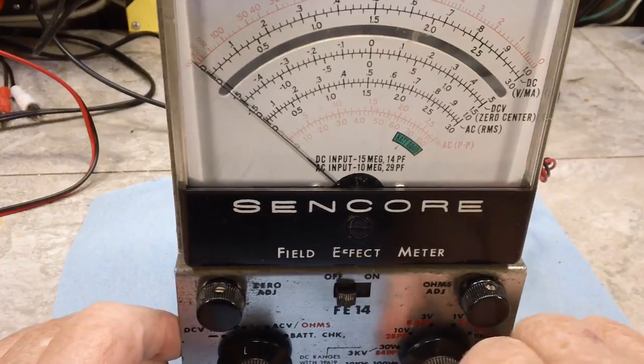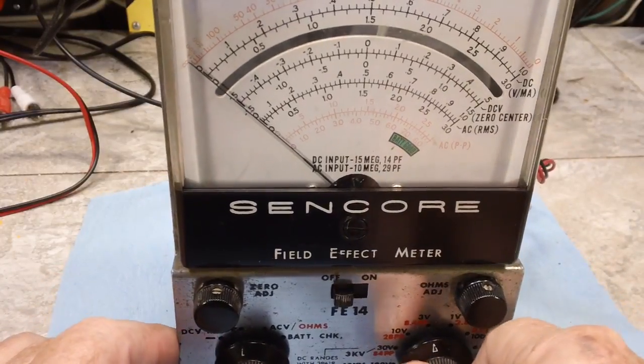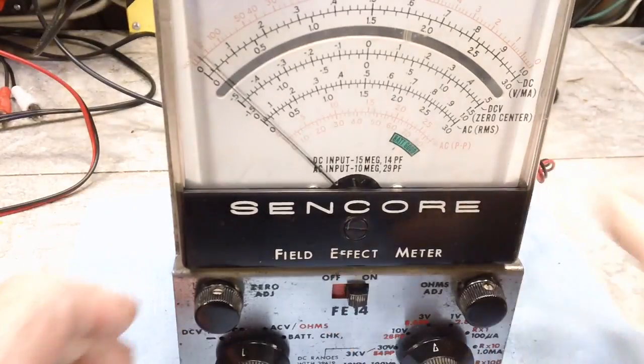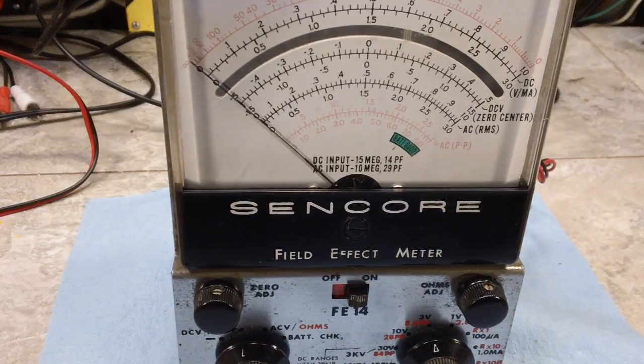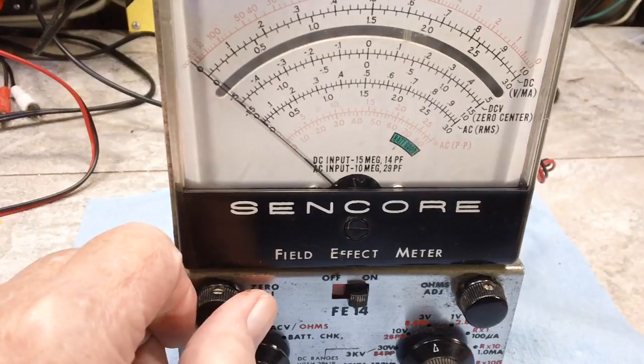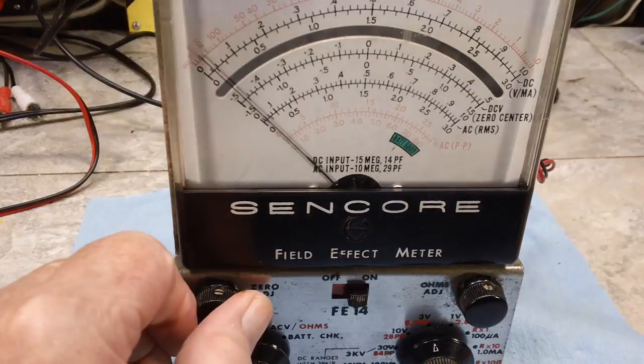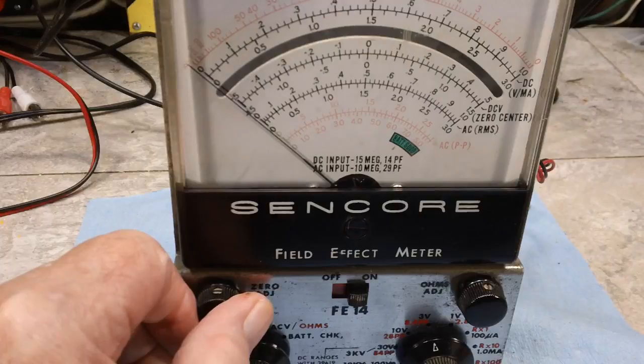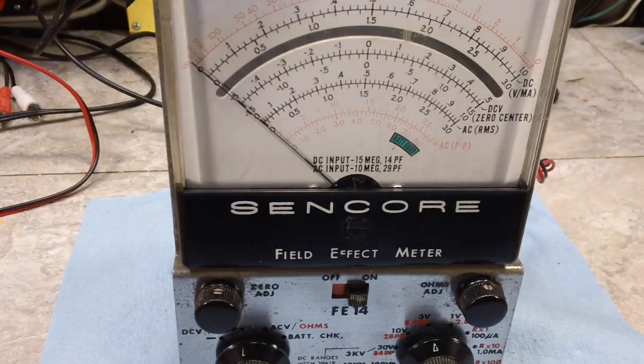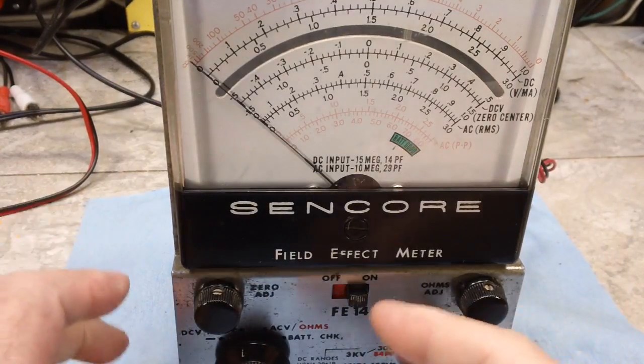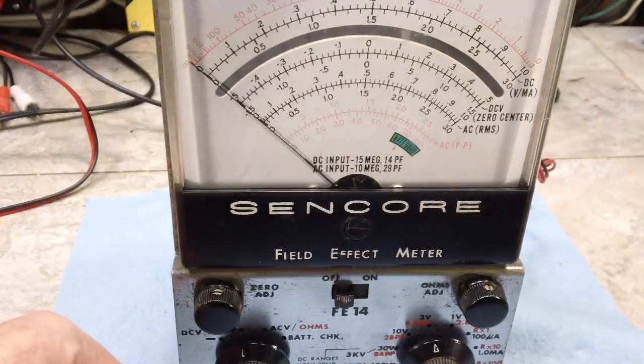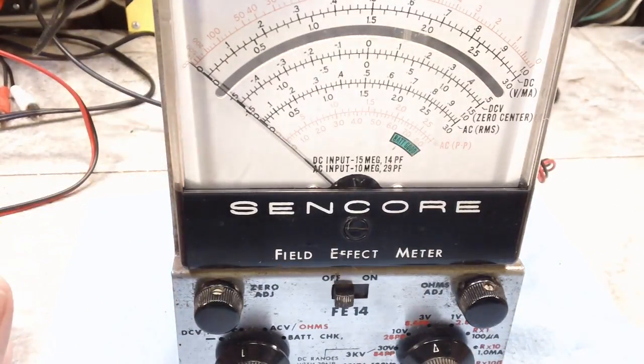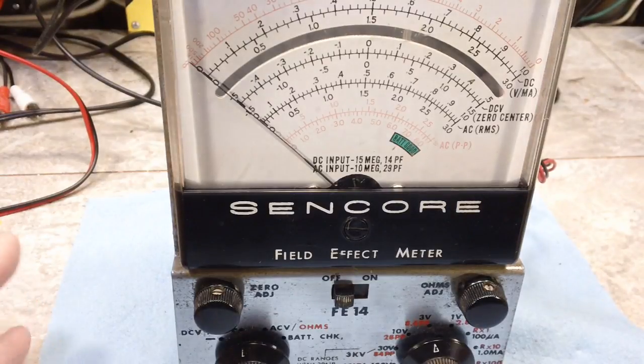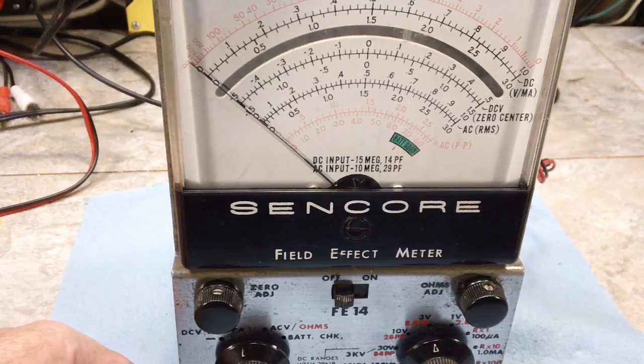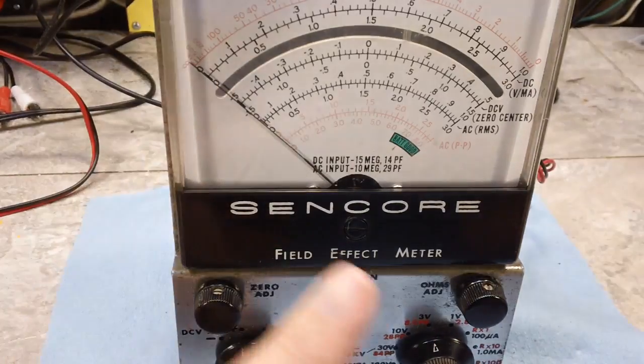Let's do this right. Put it in a voltage range. That's a 3 volt range there. So, you know, there it's on 0. So that's what this does. The DC balance makes this go where you set this right in the middle of the travel, and that's where your 0 is at. That's what that's for. So the DC balance has been set on this. So that part's good. So the rest of the calibration I cannot do. I can do the DC voltage, but we've already seen it's pretty close.